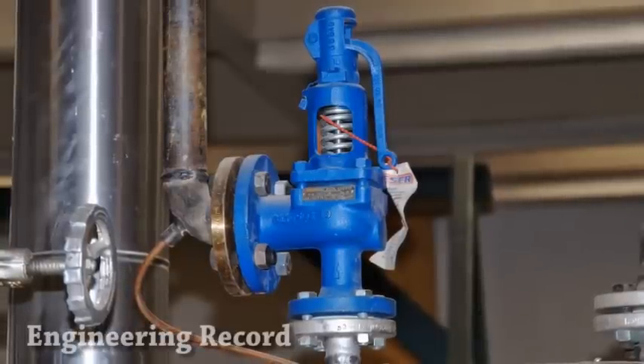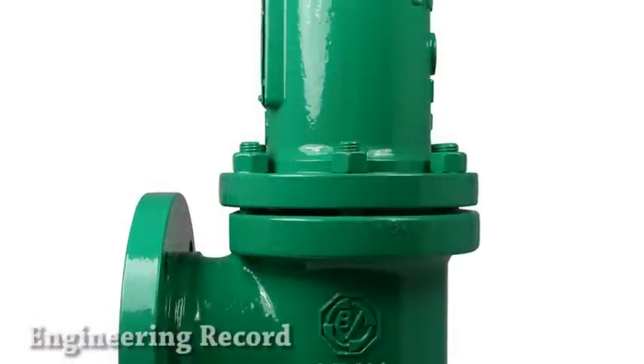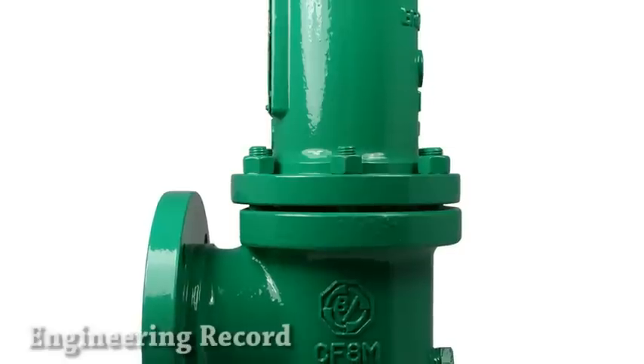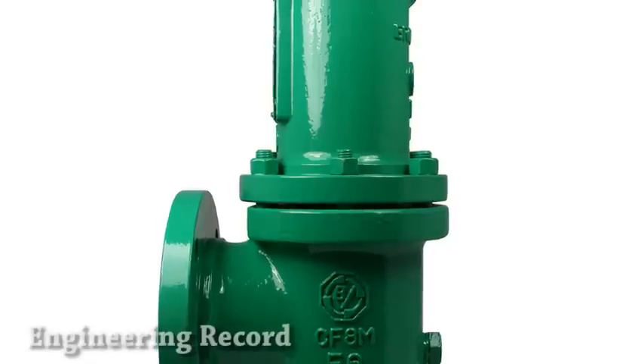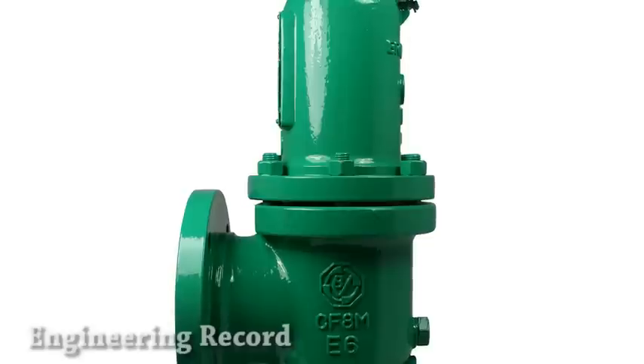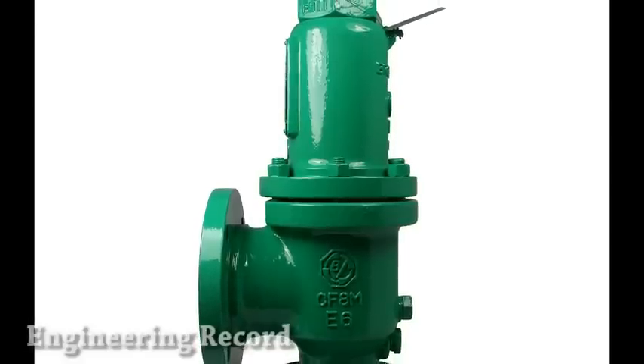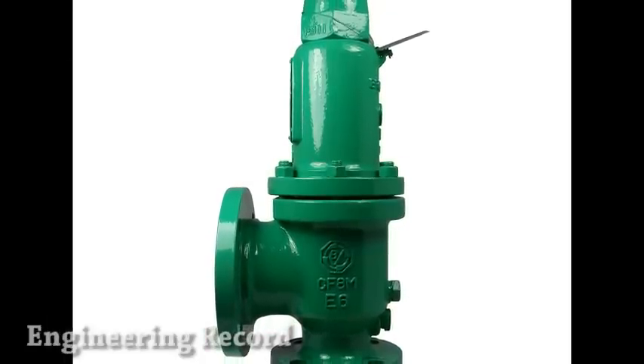A PSV serves safety, namely the immediate need for securing the process. If seen from the way it works, PSV will immediately secure the process of excess pressure by erupting or suddenly opening. Pressure safety valve is a valve used to secure the pressure on compressible fluid or gas in a pipeline or vessel. The PSV will fully open suddenly, pop, when the pressure achieves the set point.